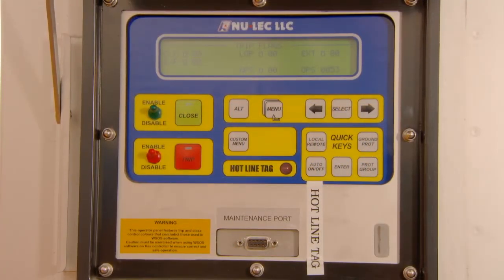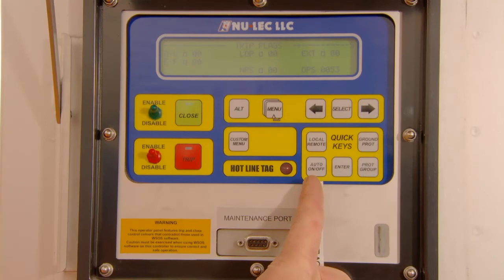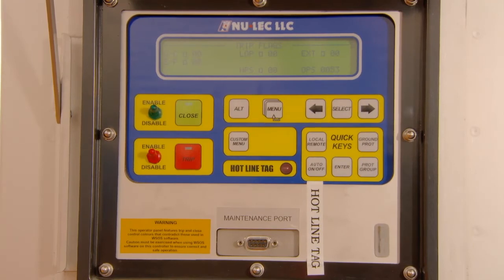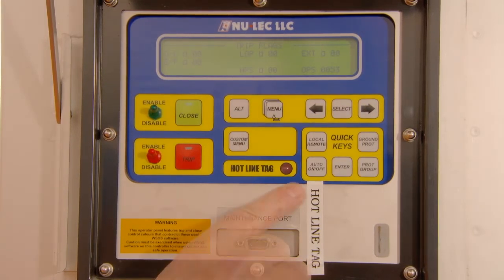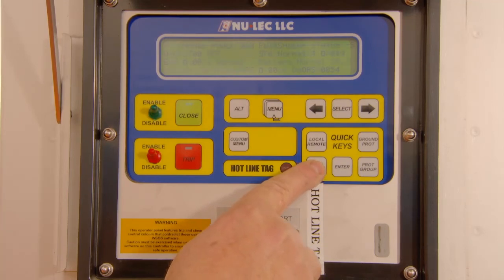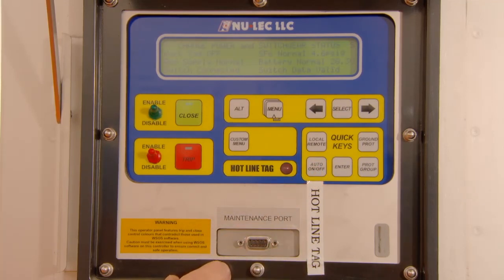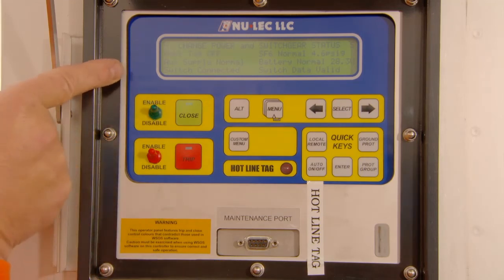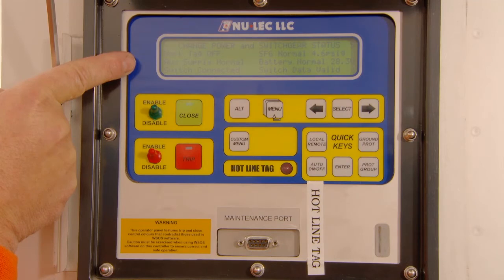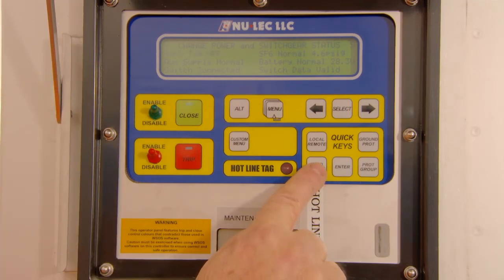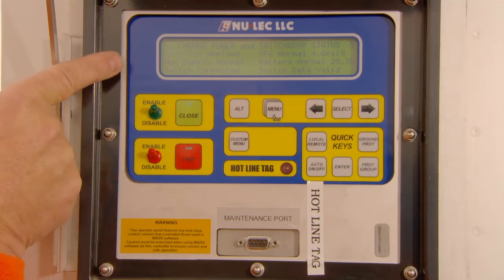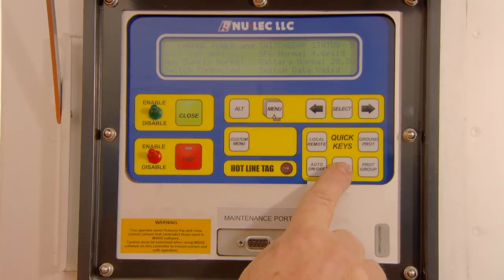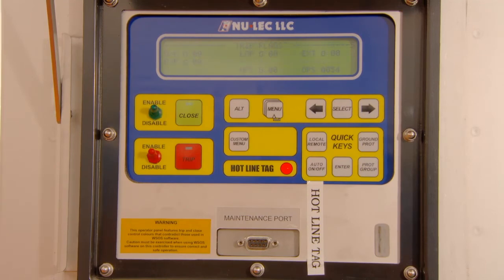Next, we will discuss the hotline tag function that is programmed to the quick action key labeled Auto On/Off. It is marked with an auxiliary white label to identify the custom programming of this key. To activate a hotline tag, press the Auto On/Off key once. You will see in the display screen the flashing words Work Tag Off. Press the button again and the display will flash the words Work Tag Applied. Press the Enter Quick Action key to activate the hotline tag. The red hotline tag LED will illuminate, indicating that the hotline tag is active.